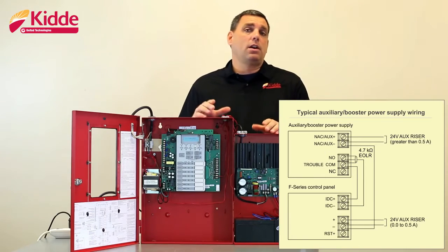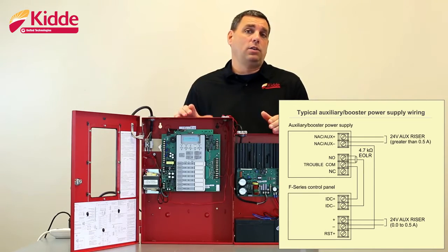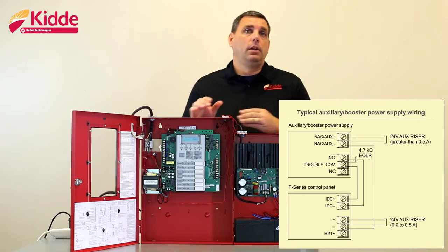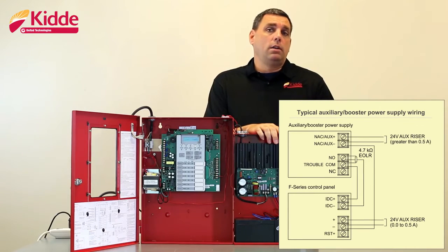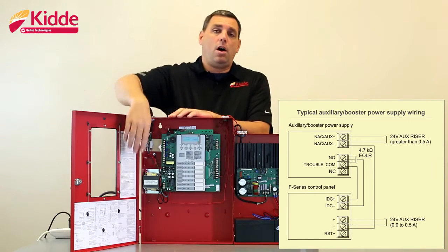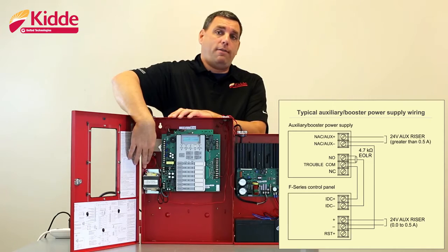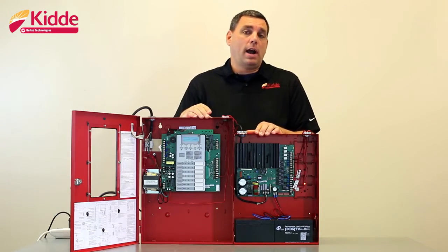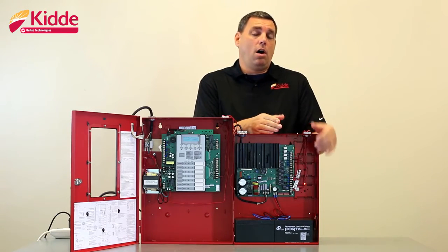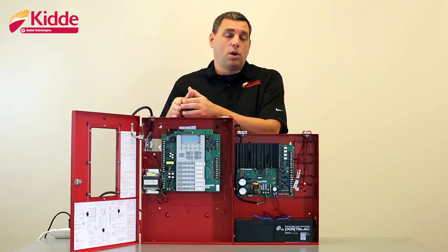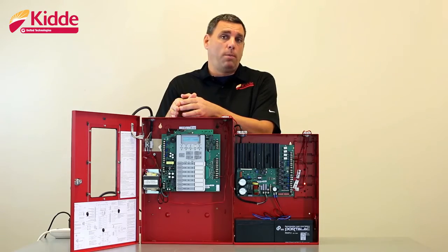We also have a figure in the FX panel manual which shows some additional wiring connections that you're going to need to interface the booster to the control panel. You're going to wire the aux power common on the booster panel back to the aux power common on the FX control panel. The purpose of the interconnect wire is so that if we get a ground fault on the auxiliary power circuit at the booster, we will generate a trouble and a ground fault back to the FX control panel.